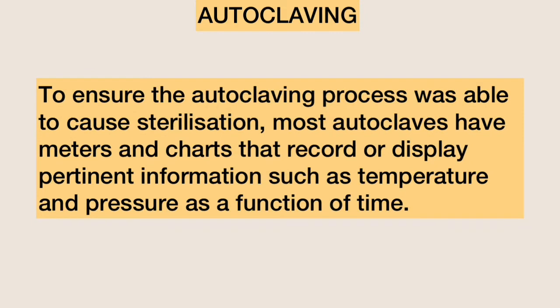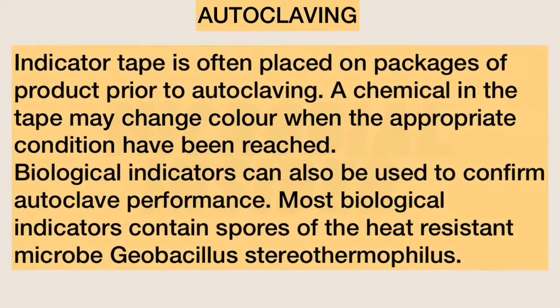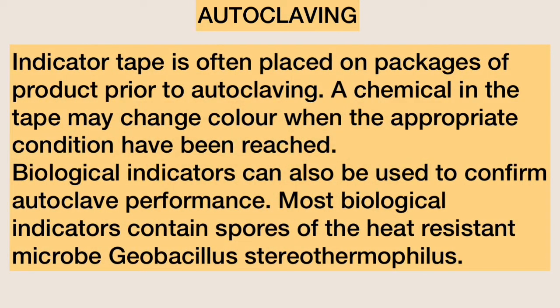To ensure the autoclaving process was able to cause sterilization, most autoclaves have meters and charts that record or display important information such as temperature and pressure as a function of time. Indicator tape is often placed on packages of products prior to autoclaving, and a chemical in the tape may change color when the appropriate conditions have been reached. Biological indicators can also be used to confirm autoclave performance.